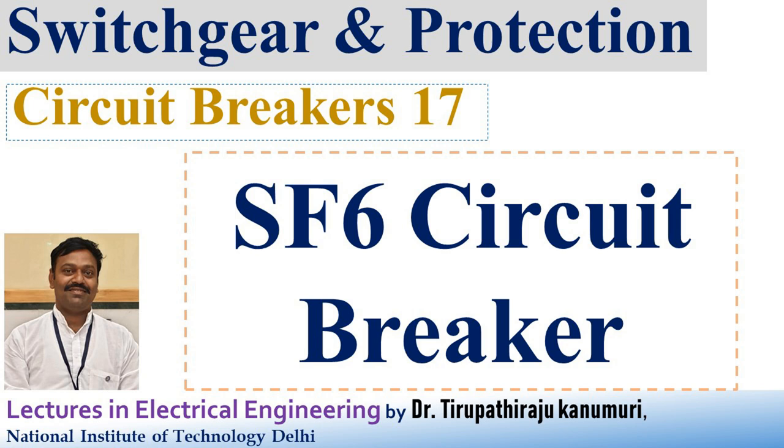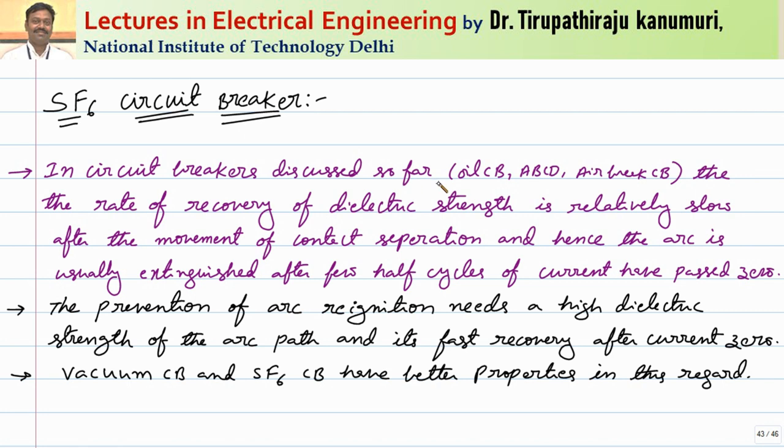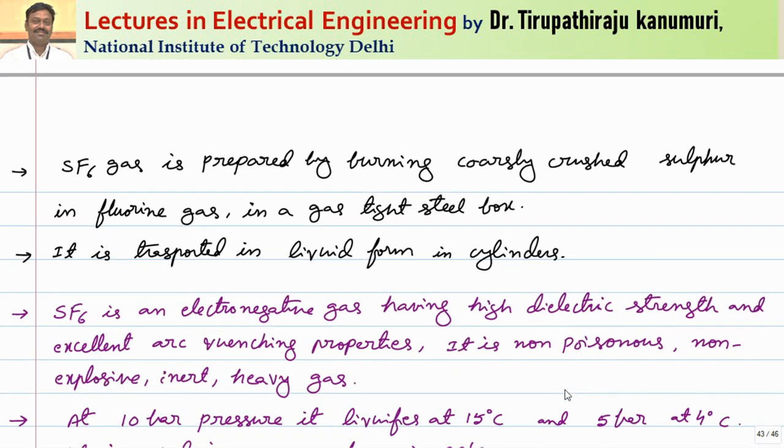Today we are going to discuss SF6 circuit breakers. In the circuit breakers discussed previously — oil circuit breakers, air blast circuit breakers, and air break circuit breakers — the rate of recovery of dielectric strength is relatively slow after contact separation, so the arc is usually extinguished after a few half cycles past the current zero. Prevention of arc re-ignition needs high dielectric strength and fast recovery, which is achieved in vacuum and SF6 circuit breakers, allowing arc extinction at the first or second natural current zero within one cycle.